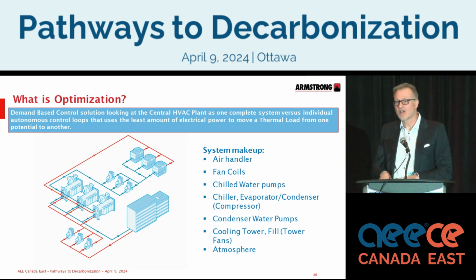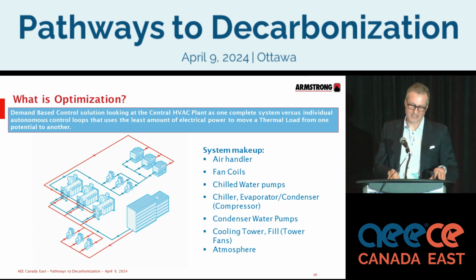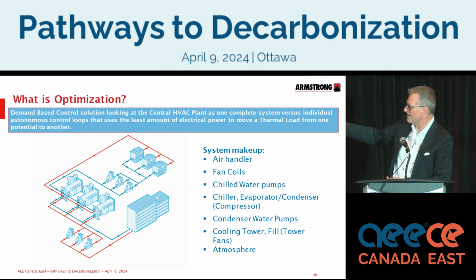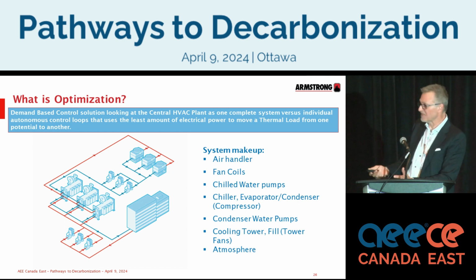When we're moving that thermal energy, we are using mechanical equipment to move it. In a chilled water plant, it's the pumps, it's the fans, it's the chiller compressor, it's the condenser water pumps, and it's the cooling tower fans. We want to look at that as a complete system. So the system makeup is the air handler, the fan coils, the chilled water pumps, the chiller with the evaporator and condenser barrel, the compressor, condenser water pumps, cooling tower fans. Now, if you look at it in second and third year mechanical engineering, it's heat transfer, refrigeration cycle, affinity laws or fan laws, heat transfer. That's the logic. That's what we're doing.